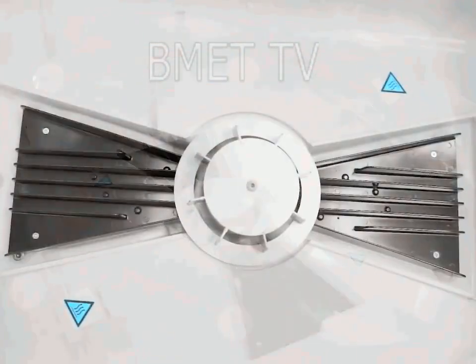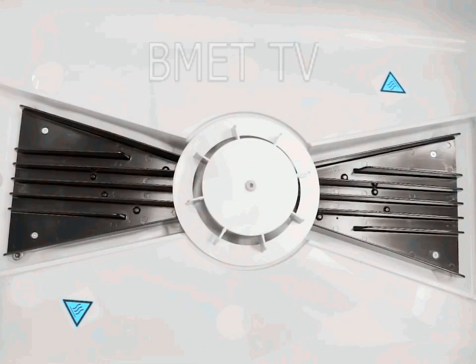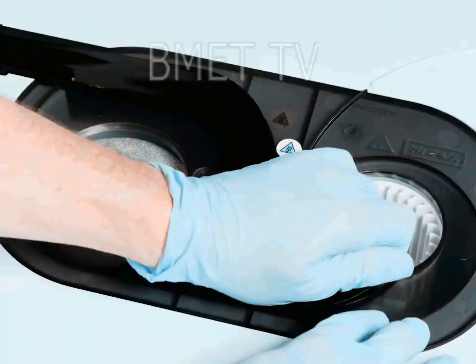First, let's look into the fan. The fan takes the filtered room air and blows it over or through the heating element and the humidifier. Without the fan, the heat cannot be conducted away from the heating element, and the heating element, and thus the incubator, would overheat. The second component is the filter.